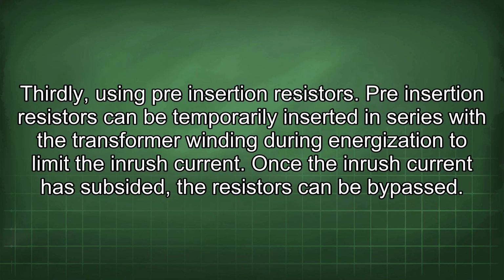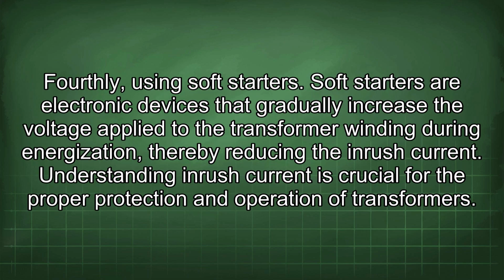Thirdly, using pre-insertion resistors. Pre-insertion resistors can be temporarily inserted in series with the transformer winding during energization to limit the inrush current. Once the inrush current has subsided, the resistors can be bypassed. Fourthly, using soft starters. Soft starters are electronic devices that gradually increase the voltage applied to the transformer winding during energization, thereby reducing the inrush current.